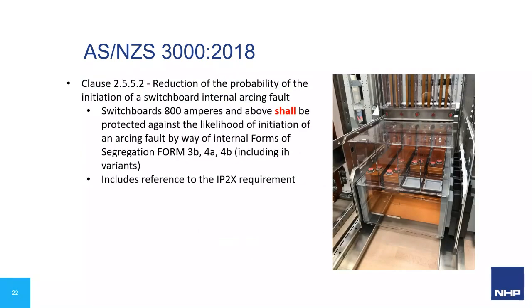The other thing AS3000 brings in as well is that switchboards above 800 amps shall be protected against the likelihood of initiation of arcing faults by way of internal forms of separation, form 3B, 4A, 4B. I'm not going to go into the detail about forms of separation, but the idea is that you're reducing the likelihood of an arc fault event starting by introducing these forms to isolate the conductors from one another. On the right hand side there, that's a photo from our Cubic switchboard system, and that's a housing variant, so an H variant of the form. That means that if you're in there and you drop a tool down onto it, the tool's never going to start an arc fault because it's never going to be able to touch those conductors. That's a way that Cubic go about it, and fairly common out there. The other one you'll see is insulation and barriers and all sorts of things. So that's an important one there.